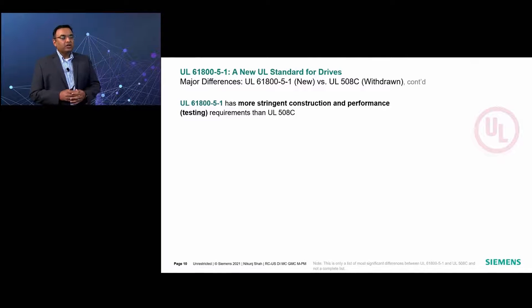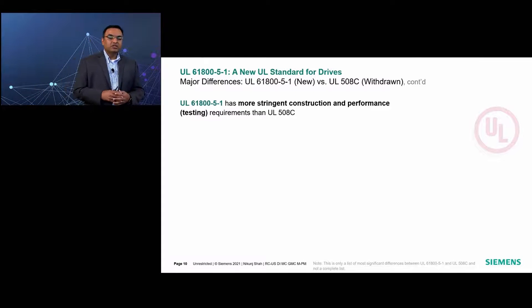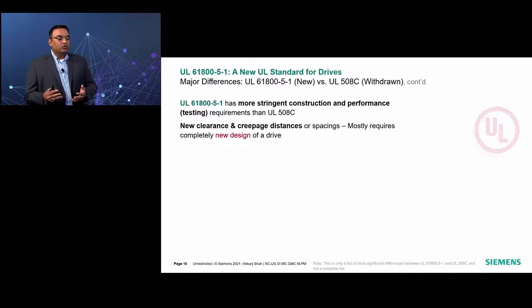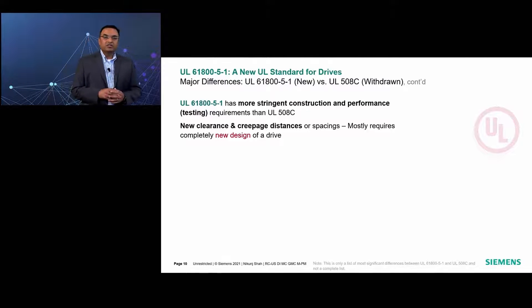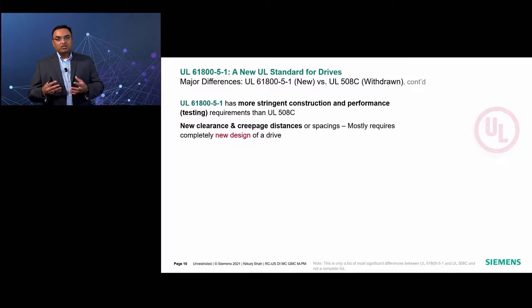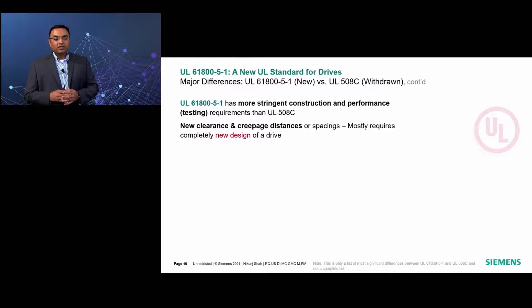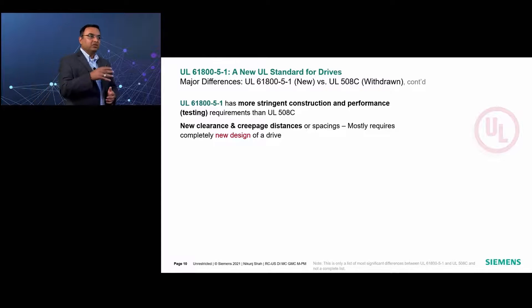Moreover, 61800-5-1 contains the most stringent construction and performance or testing requirements as compared to drives certified according to UL508C. One of the construction requirements, for example, is the new requirement for clearance and creepage distances or spacings within the drive. Because of this new addition in 61800-5-1, any existing drives certified according to 508C will require a major overhaul — a complete redesign — in order to comply with this new clearance and creepage distance requirement.